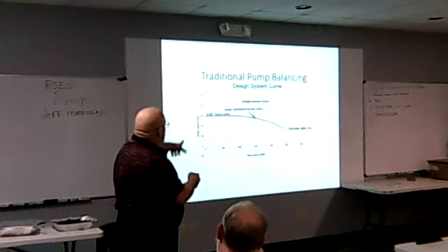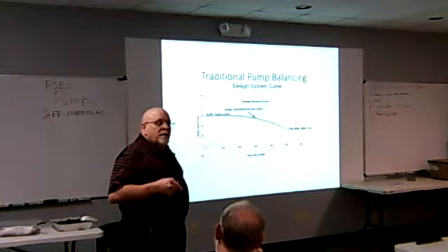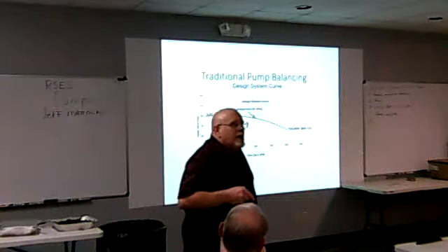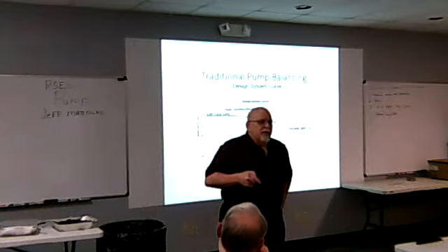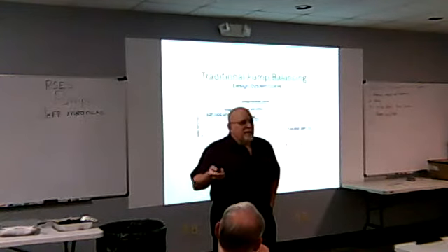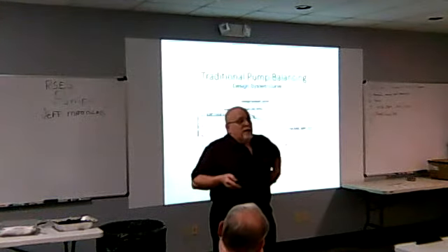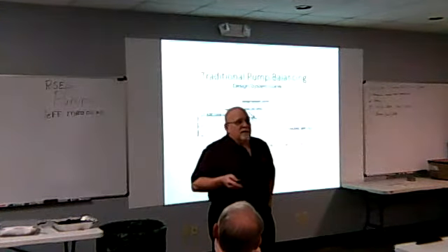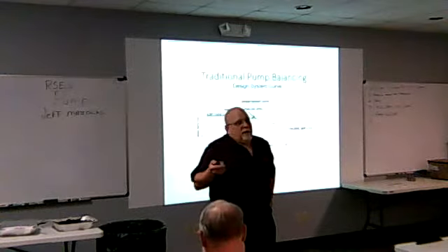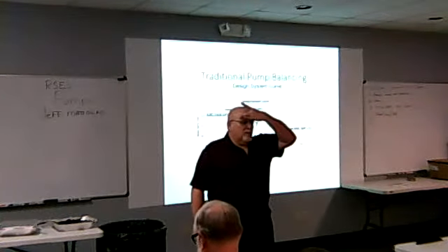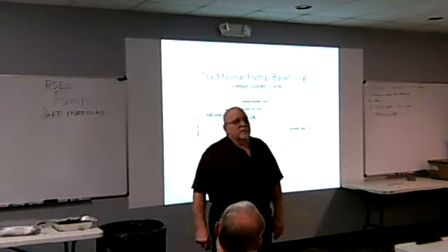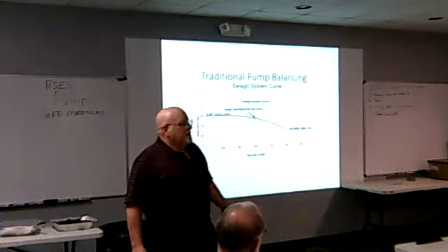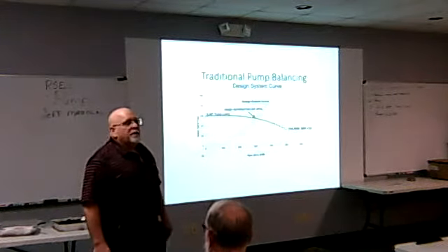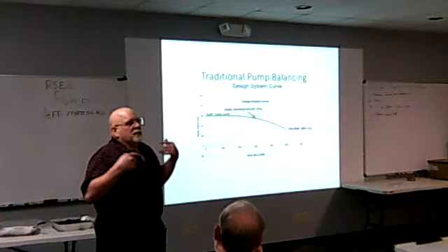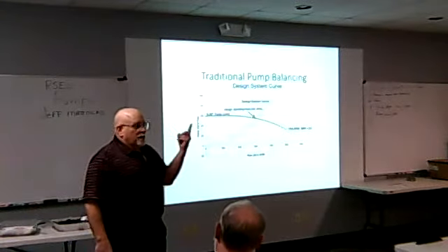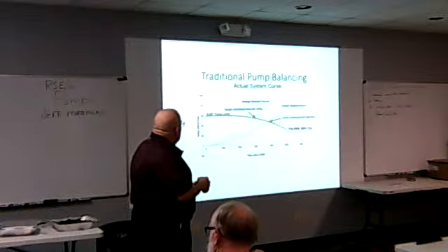Okay, Jeff, how is that temperature compensated? What's that? How's the curve temperature compensated? Oh, temperature. Well, it's just based on flow and head. I don't think the temperature matters, the viscosity change with temperature is so minor, it's really not going to affect it. Now, the liquid you put it in will change it, because then we really have to worry about viscosity, because that will change my curve. But for water, it's so minor. Specific gravity changes as well. Everybody understand what specific gravity is? It's the density of the liquid compared to the density of water. The specific gravity of water is one.